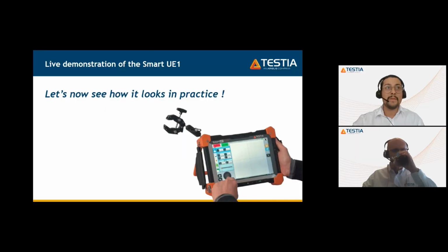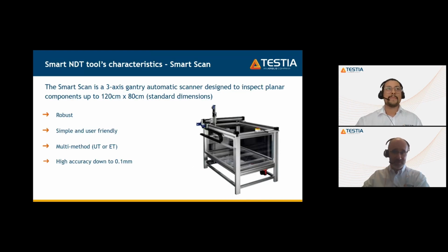So can we go to the next ones? Okay. As already said, the SMART UE1 can connect to any type of scanners or encoders. Our Smart Scan is one of them. It is a 3-axis gantry automatic scanner designed to inspect planar components up to 120 centimeters by 80 centimeters as standard dimensions. It is robust thanks to its frame made of aluminum profiles. It is simple and user-friendly. The software to define the trajectories is so intuitive that NDT beginners get immediately familiar with it in our training center after a few minutes. It is multi-method. You can connect any UT or ET instrument with TTL encoder inputs. And its accuracy is 0.1 millimeter, which allows to characterize or periodically verify ultrasonic transducer plotting acoustic beam cross sections.